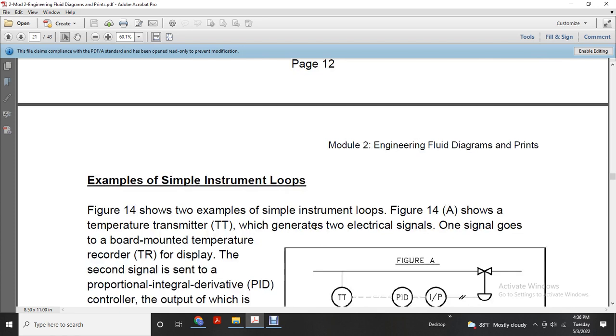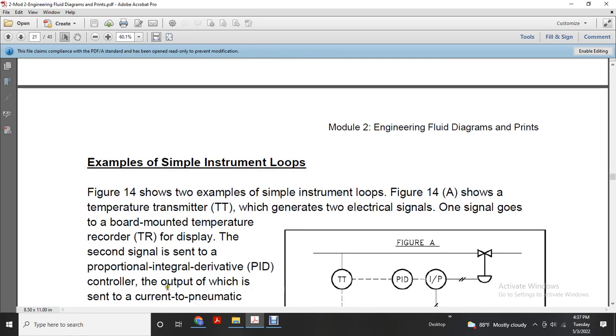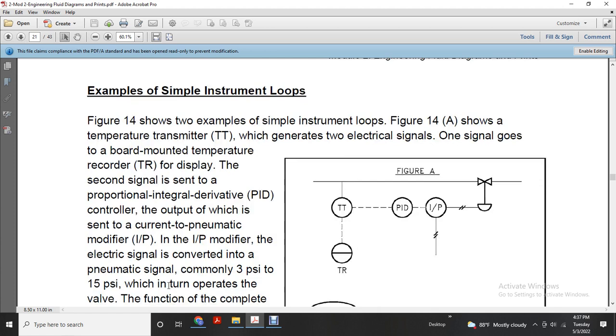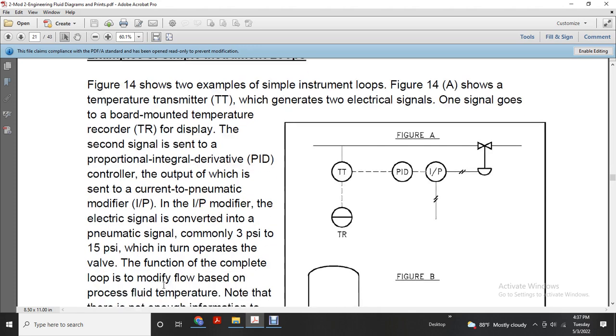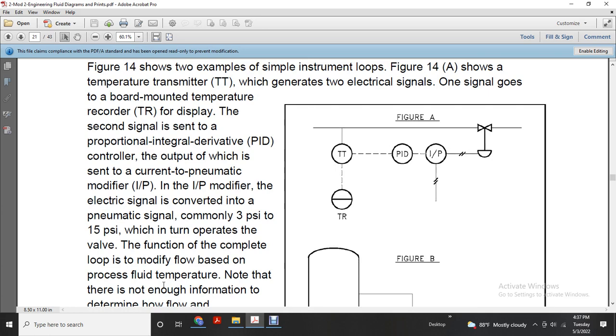Example of simple instrument loops: Figure 14 shows two examples of simple instrument loops. Figure 14a shows a temperature transmitter generating two electrical signals. One signal goes to the board mounted temperature recorder, the display. The signal goes to the proportional integral derivative controller, whose output is sent to the current to pneumatic modifier, the converter of the electrical signal to a pneumatic signal, commonly 3 psi to 15 psi, which operates the valve to complete the loop, modifying flow based on process fluid temperature.